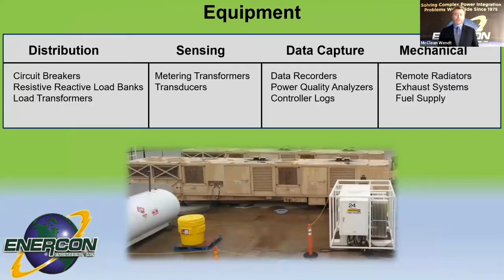So the equipment is important, and when setting up the test, we have to simulate whatever the power system is supplying. And so that's going to be a distribution system of some sort. Those will comprise circuit breakers, resistive and reactive load banks, and load transformers. So circuit breakers are important to provide protection in case there is a fault. Also for isolation, so that the unit under test can be isolated for certain tests. If we are hooked to a load transformer, if we're doing a lot of starts and stops, we may not want to be energizing and de-energizing a transformer.